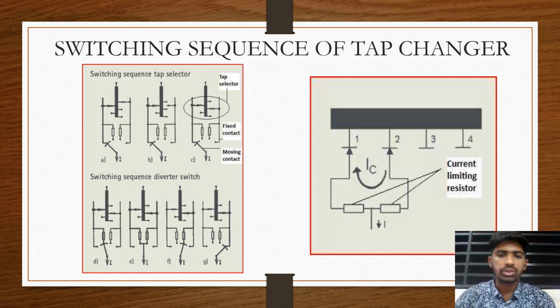Now, in order to understand the switching sequence of the tap changer, we'll take a deep look into this picture. The switching sequence happens according to the AVR feedback that we receive. A tap that is closed has to be changed to the tap that we require. After the tap is selected, the moving contact moves and closes both the taps for a while. Then it moves further, completely opens the earlier tap, and closes the tap that we require. During this process, the moving contact closes two taps for a while, due to which a circulating current will start to flow. This current needs to be minimized, so for limiting this current, we use current limiting resistors or reactors.